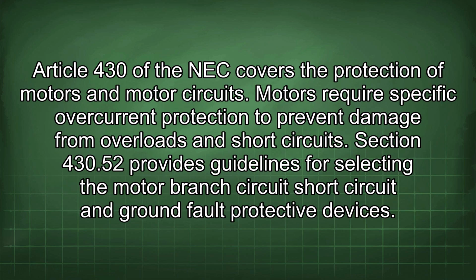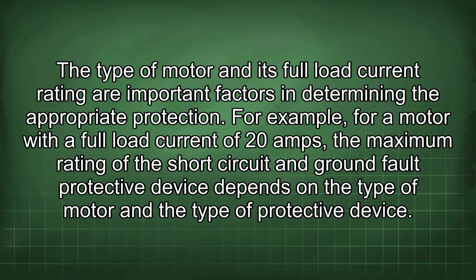Article 430 of the NEC covers the protection of motors and motor circuits. Motors require specific overcurrent protection to prevent damage from overloads and short circuits. Section 430.52 provides guidelines for selecting the motor branch circuit, short circuit, and ground fault protective devices. The type of motor and its full load current rating are important factors in determining the appropriate protection.